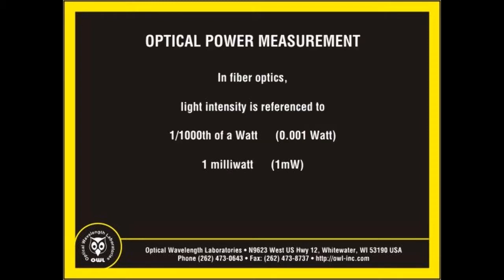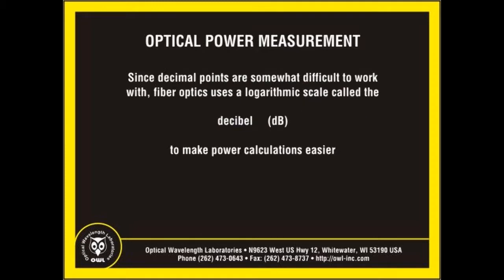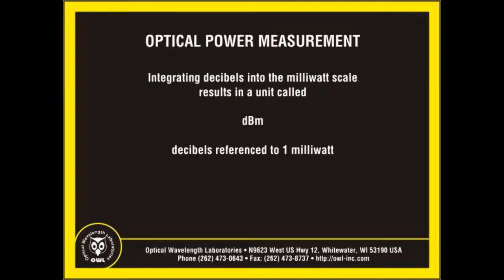The same goes for fiber optics, except the light intensities are referenced to one one-thousandth of a watt, or one milliwatt. Just as all light bulbs are compared to one watt, all fiber optic light sources are compared to one milliwatt. However, working with decimal points can be somewhat difficult, so fiber optics uses a logarithmic scale called the decibel, or dB, to make calculations easier to understand. When integrating decibels into the milliwatt scale, we end up with a measurement unit called dBm, which is also referred to as decibels referenced to one milliwatt.